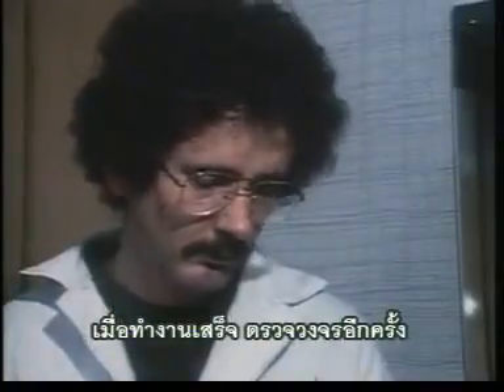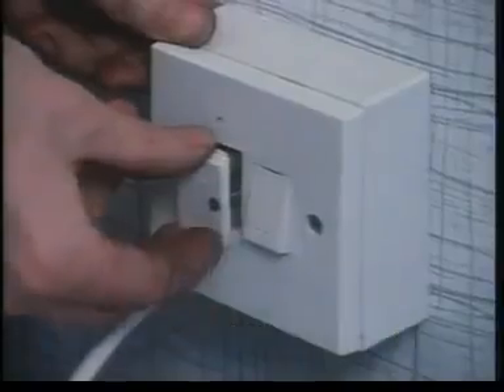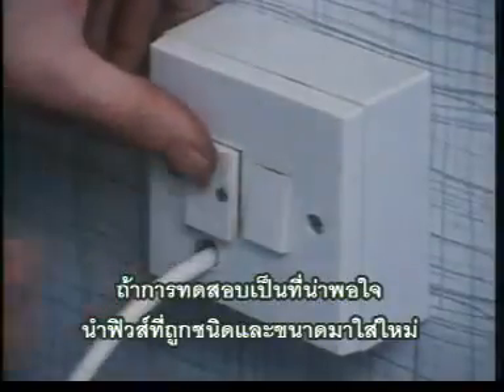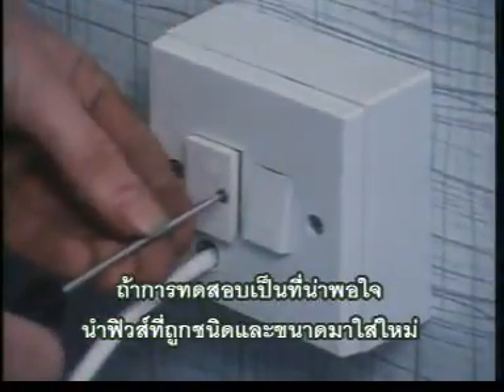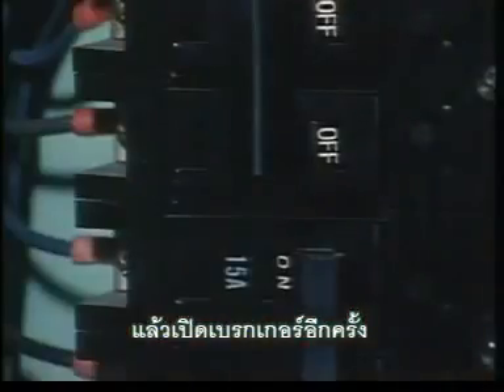When the work is finished, the circuit must be checked again. If the test is satisfactory, new fuses of the correct size and type should be put into the circuit, or the circuit breaker can be reset.